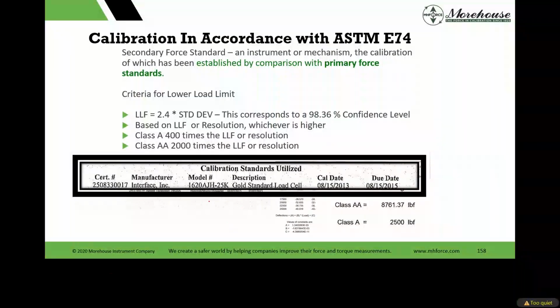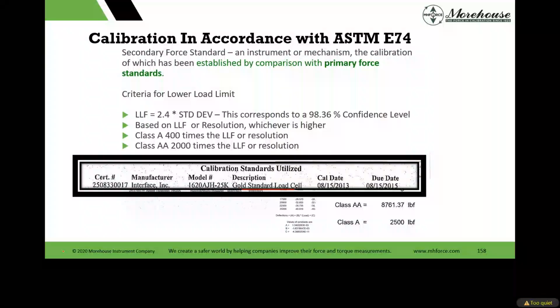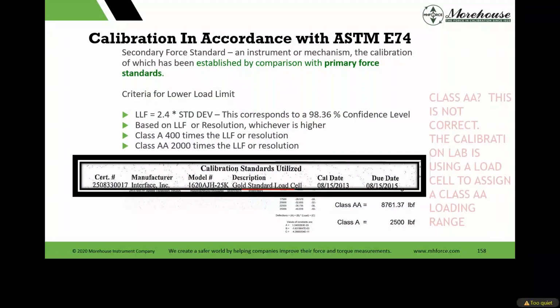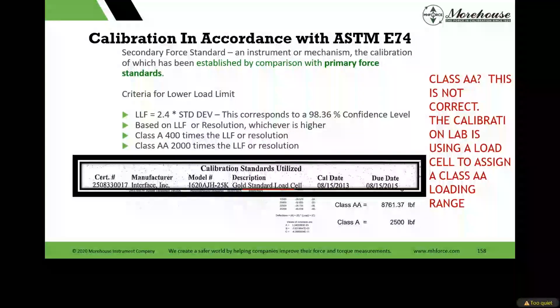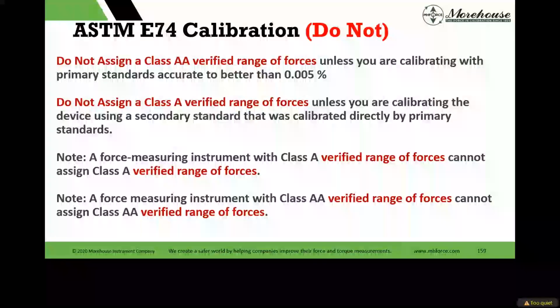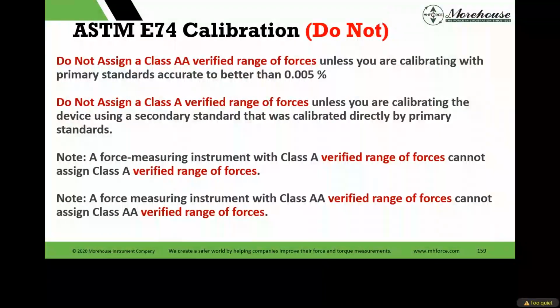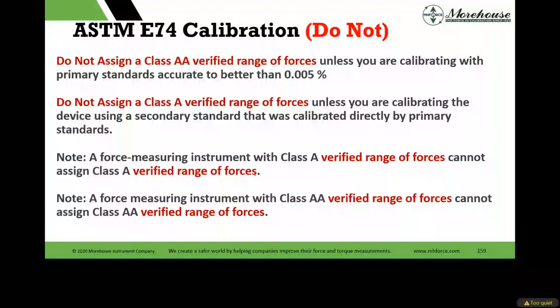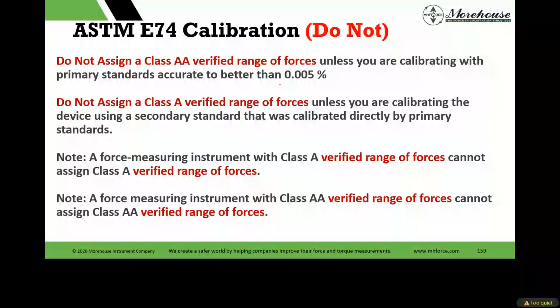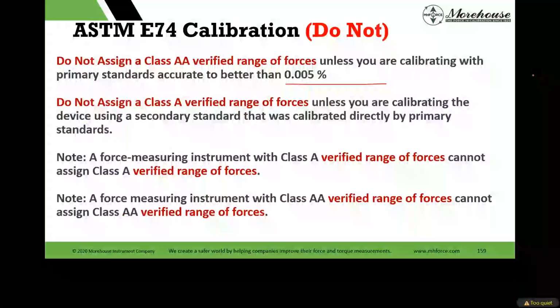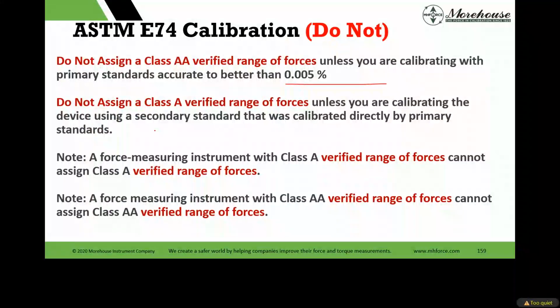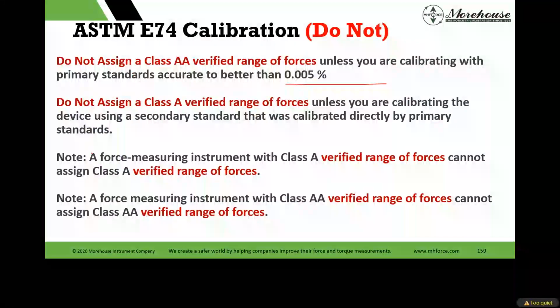they said, hey, I have this gold standard. This is a great load cell, this gold standard, and I'm assigning a class double A. You can never do that. You have to use primary standards, which is dead weights. That's all this is about. I fully think if you're using interface gold standards, great load cells, nothing bad to say about them. So do not assign a class double A range of forces unless you're calibrating with primary standards better than 0.005 %. And then do not assign a class A unless you're calibrating a device that has a class double A verified range of forces.